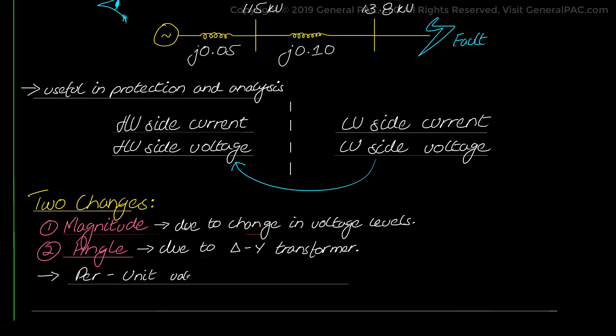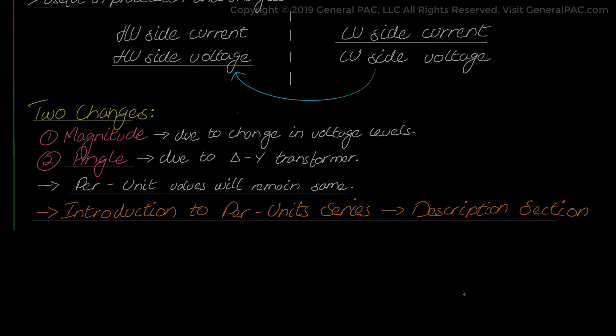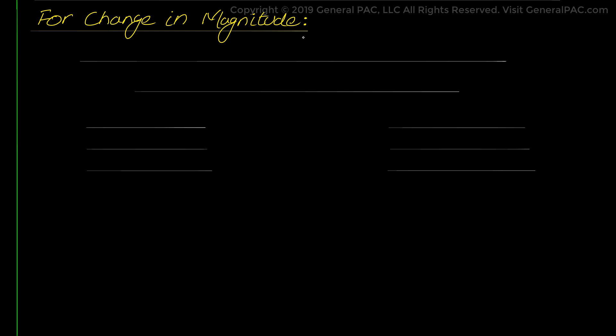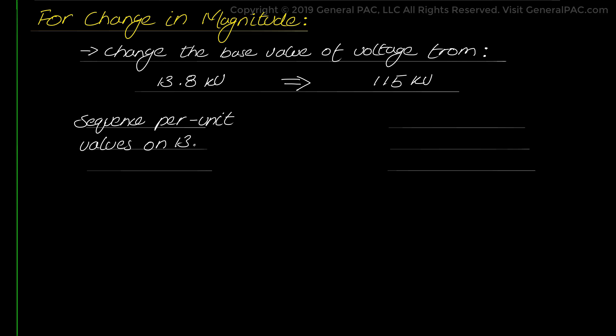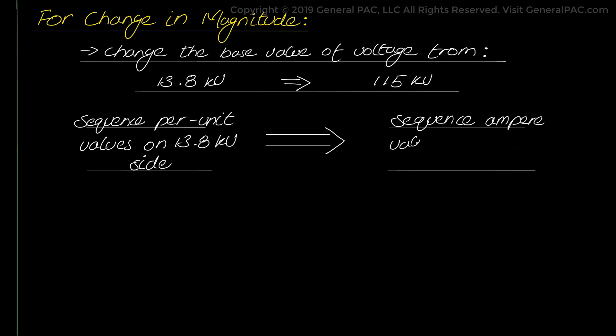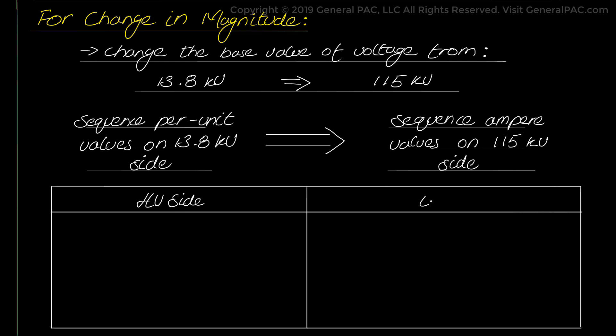Per unit values of sequence voltage and current quantities will remain the same — this is one of the benefits of the per unit system, which we viewed in the introduction to per unit series by GeneralPAC. To account for the change in magnitude as a result of analyzing the fault on the high voltage side of the transformer, we simply change the base value of the voltage from 13.8 kV to 115 kV. This allows us to convert the sequence per unit values of currents calculated earlier to the sequence ampere values reflected on the 115 kV side. The table below summarizes the changes in magnitude concepts.